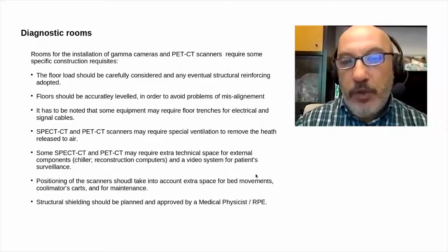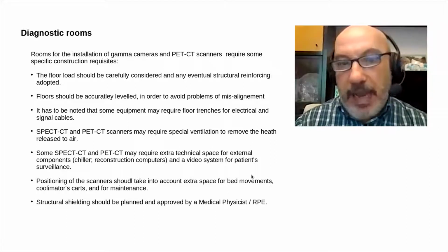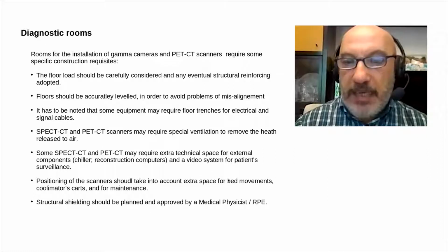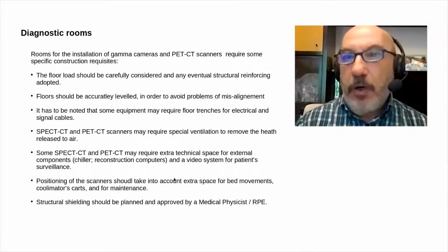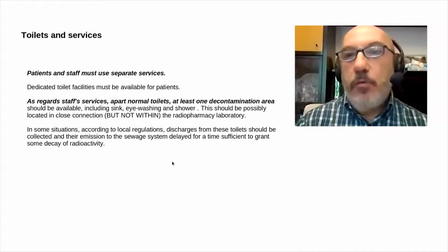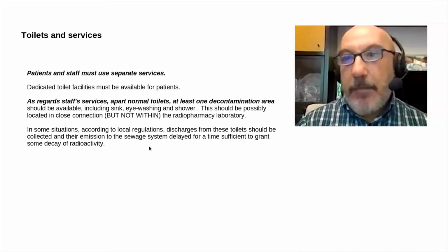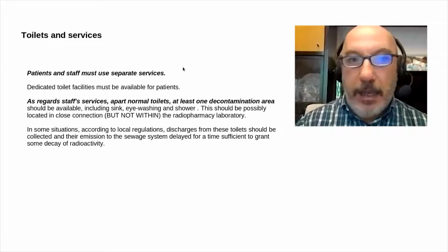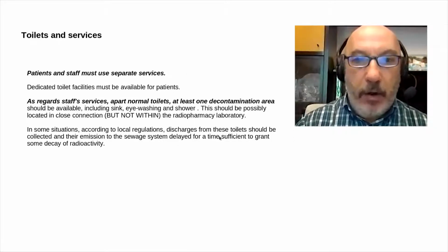Furthermore, for gamma cameras it is always to be considered that it is necessary to have all the proper space in order to allow the movement of the bed, and particularly the movement of the collimator cart from its storage position to the collimator change position. Toilets and services in the nuclear medicine department should be clearly separated for patients and for staff, and it is quite clear, in order to avoid any non-justified risk of contamination.